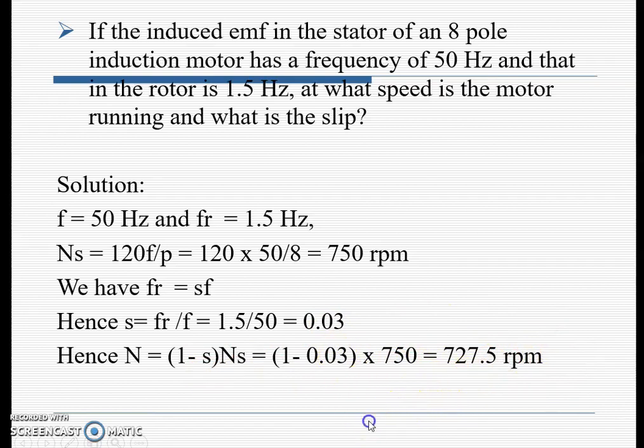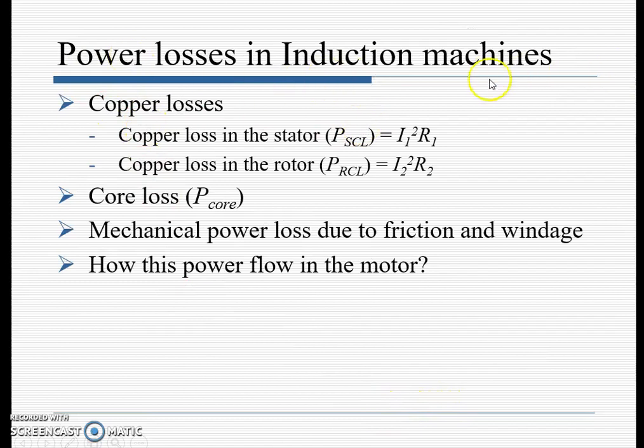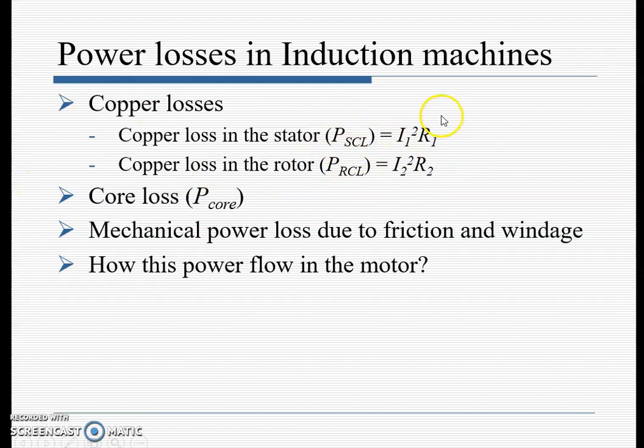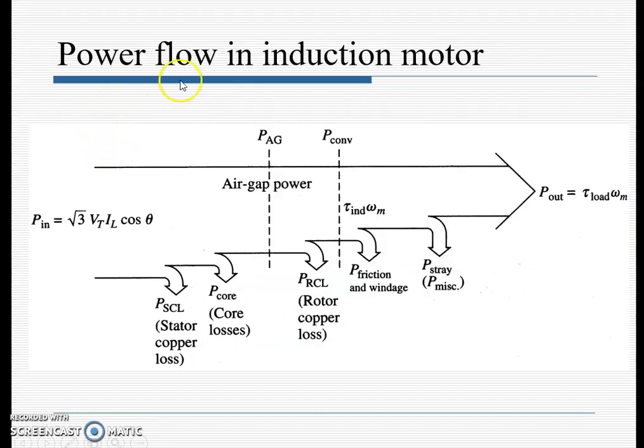Next are the different types of losses in the induction machine: copper losses in the stator (I₁²R₁), copper losses in the rotor (I₂²R₂), core losses, and mechanical power losses due to friction and windage. In the power flow of the induction motor, the input power is √3 · V · I · cos φ, where cos φ represents the power factor.